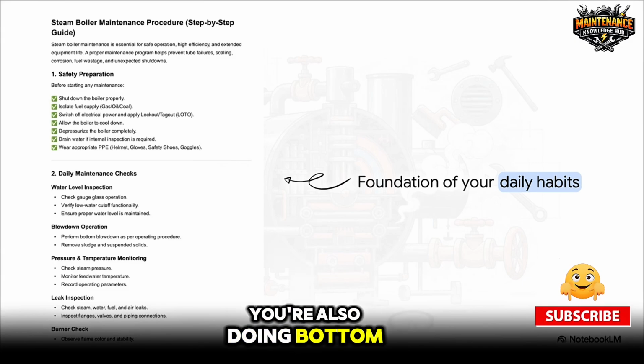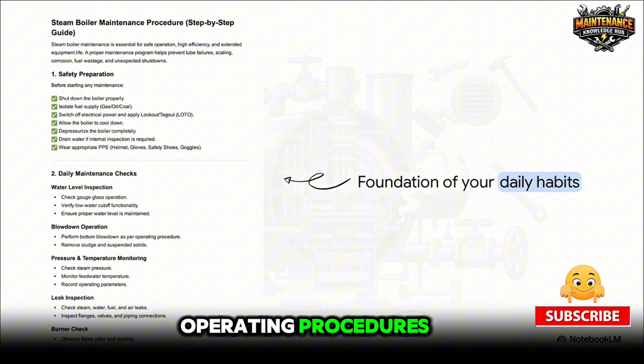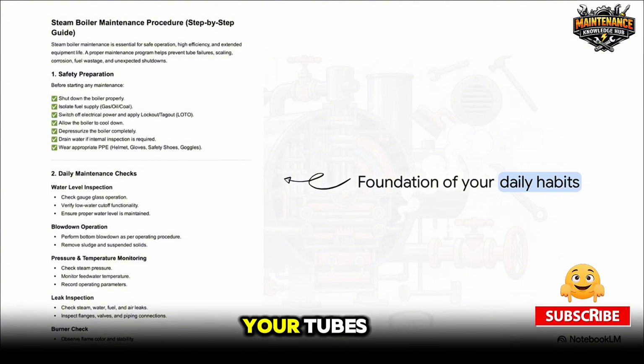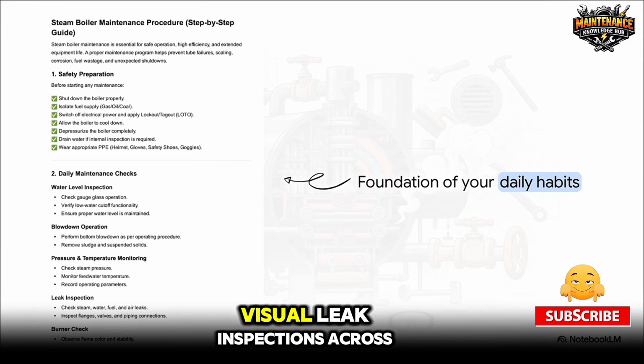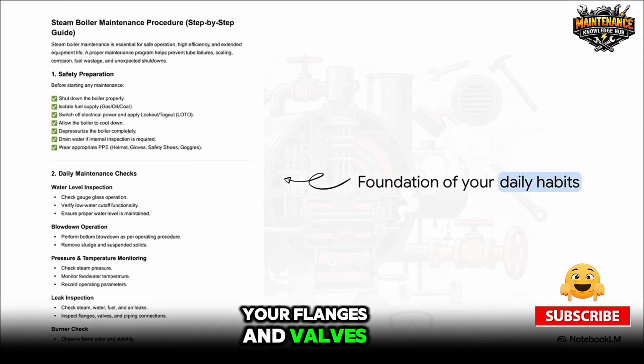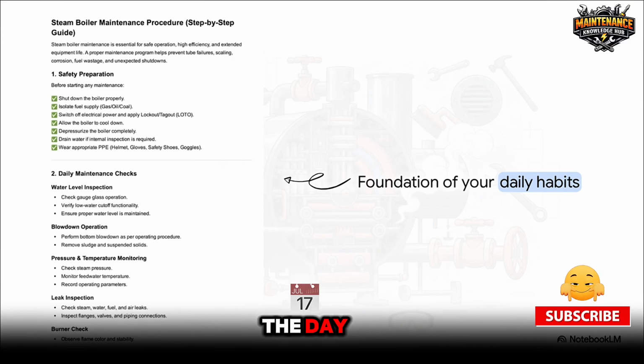You're also doing bottom blowdowns, right, according to your operating procedures, to flush out sludge and suspended solids before they can bake onto your tubes. Add in some quick visual leak inspections across your flanges and valves, and boom, you've secured the day.